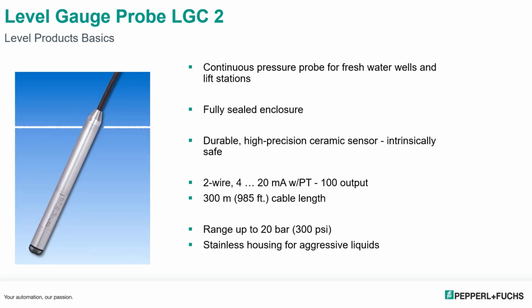The level gauge probe, LGC2, which is your environmental probe, is basically used for freshwater wells and lift stations. It can also be used for wastewater areas. The nice thing about this is you can get it in a 300-meter cable, so it's very suited for very deep wells. And it can be fully submerged in the medium. It's a fully sealed enclosure, and you can make them intrinsically safe. Range is up to about 300 psi.